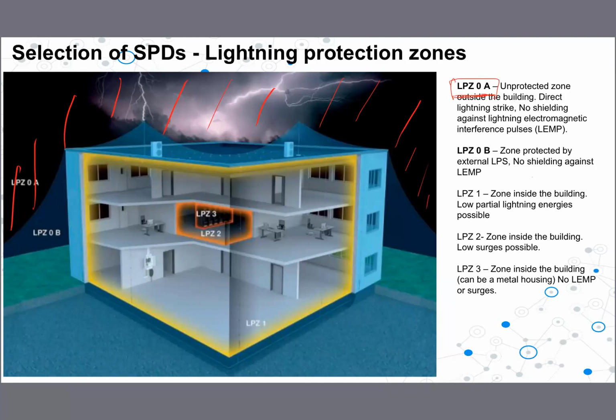Then zone 0B. Zone 0B means, let's color in a different color, this area, still outside the building, but that area is covered by the lightning protection system. Now if you use the rolling sphere method to determine the lightning protection system, it will be like this. So you know that the touching points are vulnerable, unprotected. Below the touching points, this area is protected by the lightning protection system. So this zone is protected, but there is no shield against LEMP, lightning electromagnetic interference pulses. If there is a lightning strike nearby, interference can happen in the equipment in this area also.